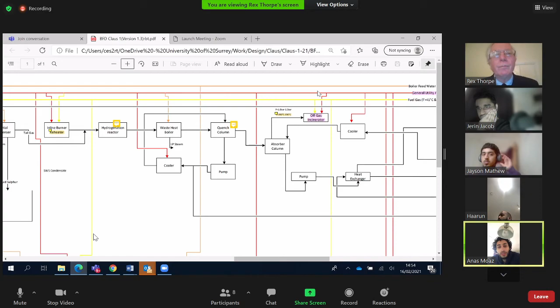Well, the first thing to say is this: you don't ever do that. You don't ever use your own steam. What you do is put any steam you generate into the steam main, and take steam from the steam main. This has the advantage that when you start up, you've always got connections to the steam main that allow you to run any unit in any order. Also, if you have a problem with the boiler, it's the utility manager's problem to supply you with steam, not yours. For every ton of steam you put into the steam main, the utilities manager gives you credit, and for every ton you take out, they charge you. So it makes no difference to you that you never use your own steam - you just sell it.